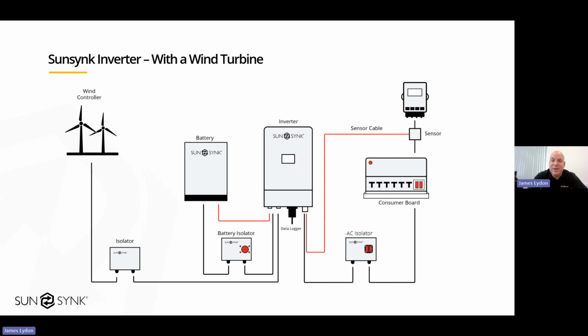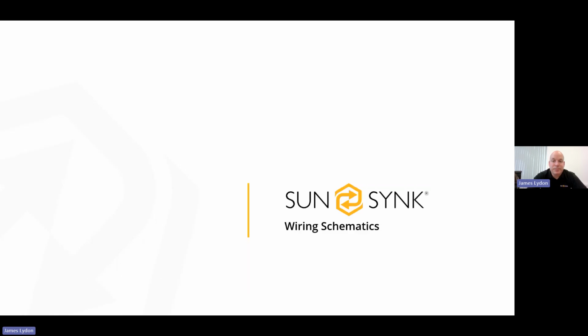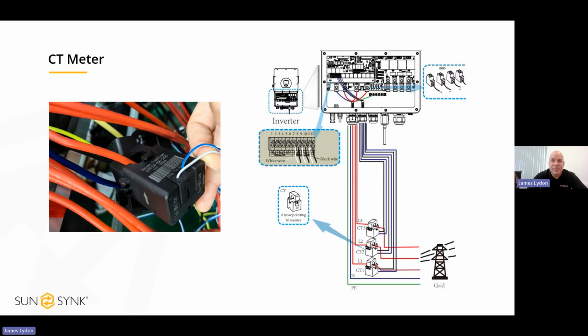So if you imagine with PV, if the battery's full and you're not exporting, the inverter will automatically clip the PV generation. You can't clip wind. So the wind power always needs somewhere to go. So that dump load is typically a heater, just a big resistive load, and that will dissipate any generated excess power as heat.